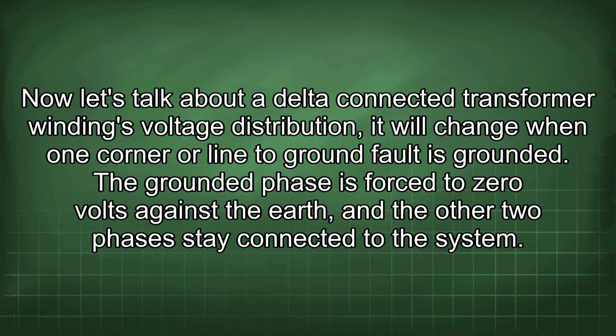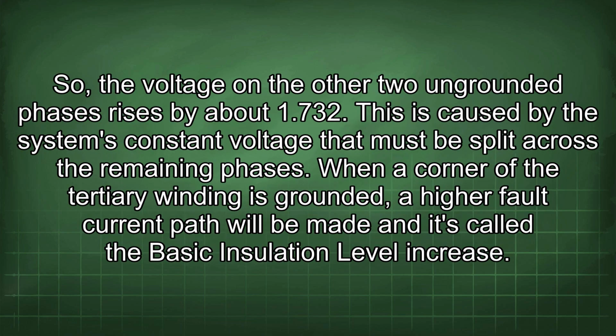Now let's talk about the delta-connected transformer winding's voltage distribution. It will change when one corner or line to ground fault is grounded. The grounded phase is forced to 0 volts against the earth, and the other two phases stay connected to the system. So, the voltage on the other two ungrounded phases rises by about 1.732. This is caused by the system's constant voltage that must be split across the remaining phases. When a corner of the tertiary winding is grounded, a higher fault current path will be made, and it's called the basic insulation level increase.